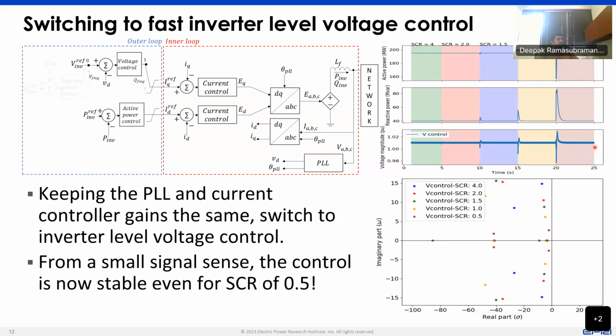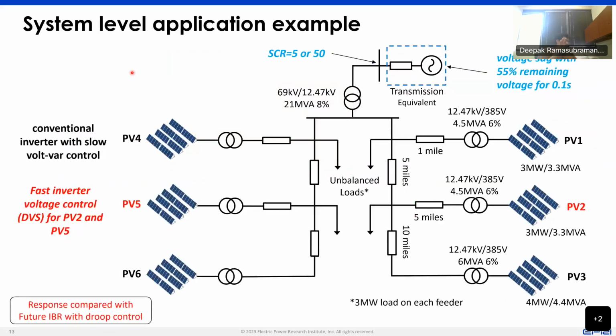Now, this is not meant to say that every inverter, if it goes down to this voltage control at the inverter level, will automatically become stable. There are concepts of controller tuning that come across for every controller in the system. But if this is done carefully, in a robust manner, then even if we keep everything else the same inside this inner loop, you can still have an improved response, improved reliability of the network by moving from reactive power control to voltage control at the inverter level. So here the hierarchy of control plays a crucial role in determining some level of stability that we want on the network. The previous examples were for a single machine infinite bus case.